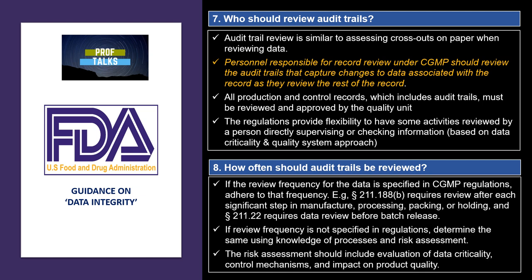How often are audit trails reviewed? If there is a regulatory requirement, it should be complied with and the audit trails reviewed accordingly. For example, USFDA 21 CFR Part 211.188 requires review after each significant step of manufacturing and processing, while 211.22 requires data review before batch release. If review frequency is not specified, it is up to the organization to determine the frequency using knowledge of the specific process and a risk-based approach. The risk assessment should include evaluation of data criticality, control mechanisms, and impact on product quality.